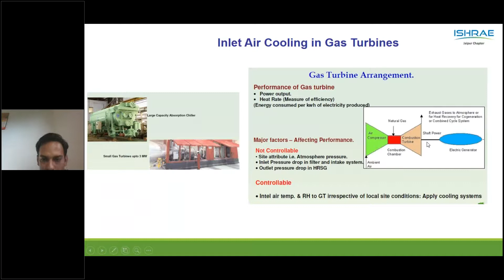The inlet air turbines are mostly designed for 15 degrees Celsius and relative humidity of 60%. As our site conditions are at roughly 40 degrees Celsius or more, there is severe deterioration in the power output of the gas turbines.